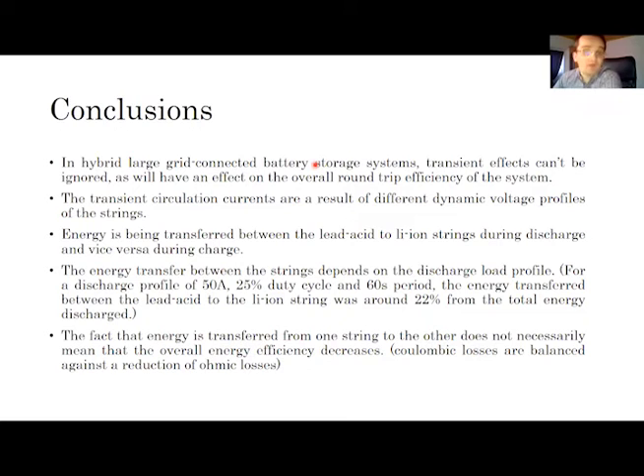And of course we have the energy transferred between the strings. If we have a pulse train discharge, then on each pulse we're going to have some energy discharging from lead acid to the lithium-ion string, and then to the load. How much are we talking about? For example, for a 50 amp discharge pulse train, with a period of 60 seconds and 25% duty cycle, the energy transferred between lead acid and lithium-ion string can be around 22% of the total discharge energy.